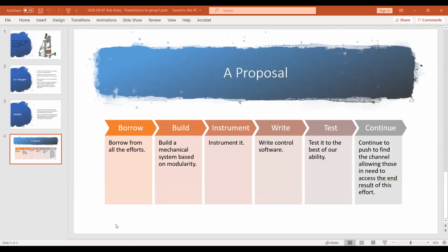Okay. Right now, we're at what we would call the initial planning stage or the design input phase. There's a specific process the FDA wants you to go through. It's called CGMP, which in itself, you'll spend hours and hours reading on. It does take a lot of time to properly design these things. The thing that we're trying to look for here is a basic systems requirement and basic safety requirement.